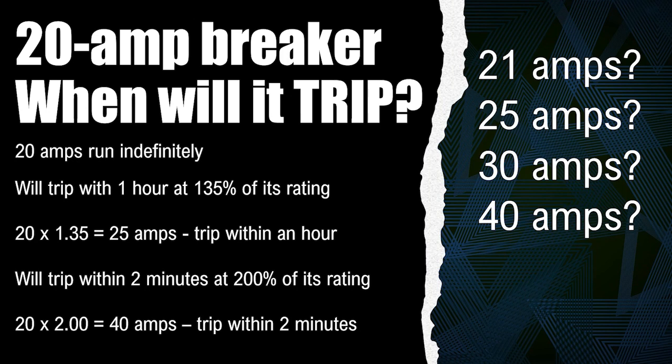Well, if I did a quick Ohm's law calculation, or I looked on the nameplate of that piece of equipment and it's supposed to run at 12 amps and I'm tripping within two minutes, there's a chance that there's something wrong there. So you can use all of these things that you learn to help you troubleshoot, to help you solve problems, to look cool out on the job when you're talking about circuit breakers.